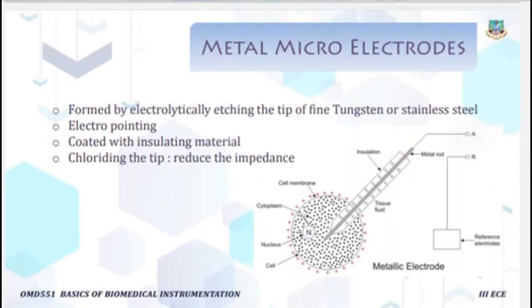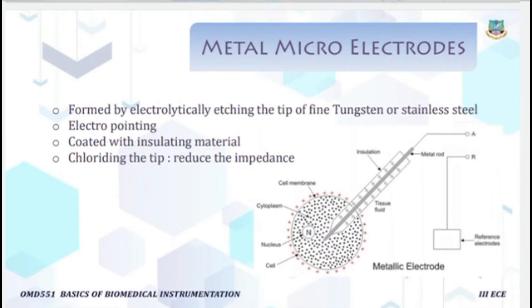The first type is the metal micro electrode, also called metallic electrode. Metal micro electrodes are formed by electrolytically etching the tip of a fine tungsten or stainless steel wire to a fine point. This technique is called electro-pointing. The metal micro electrodes are coated almost to the micro tip with an insulating material.